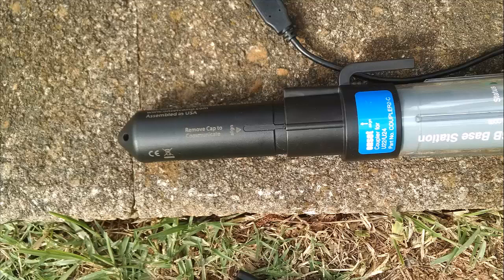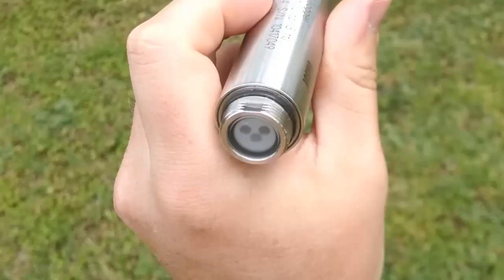To link to a logger, you first need to gently and carefully unscrew the end cap. Do not use any more pressure than necessary, as this may damage the pressure transducer. Attach the proper adapter to the base station. For the plastic housed loggers, there's a notch in the adapter which lines up with a ridge on the housing to make sure it is connected properly. For the stainless steel loggers, there's a flat edge which aligns with the adapter, and this makes sure it connects properly. When you put the end cap back on, again, be very gentle and careful. Twist slowly and do not try to over-tighten the cap, or again, you may damage the instrument.